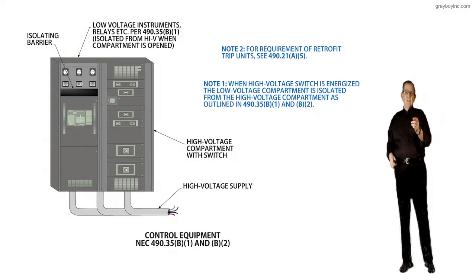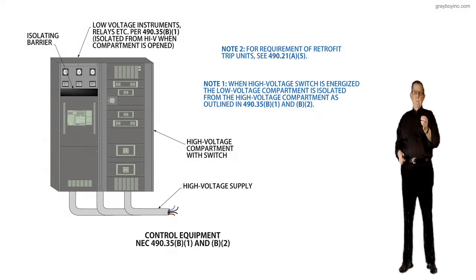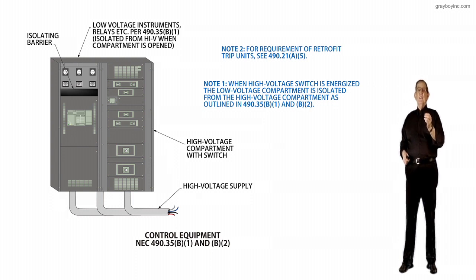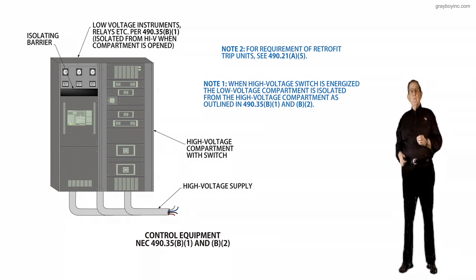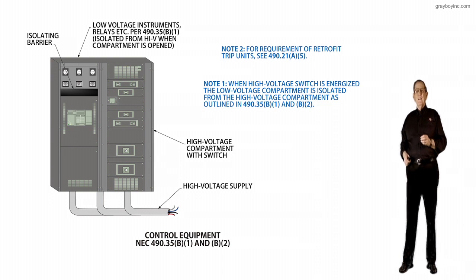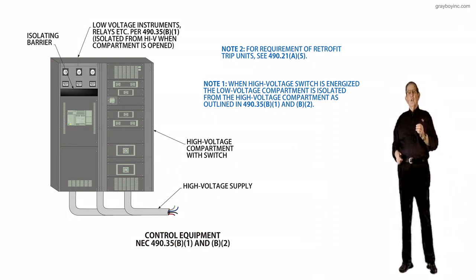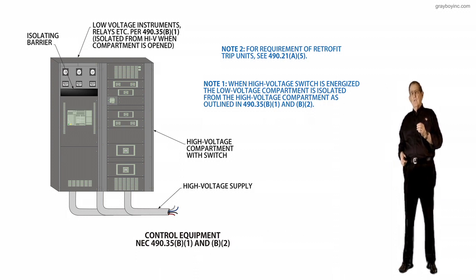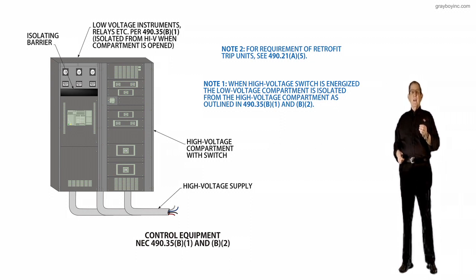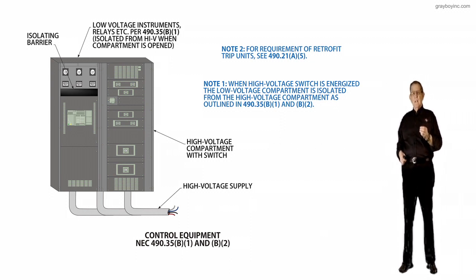This illustration deals with control equipment in accordance with 490.35 B as in boy 1 and B 2. The purpose of the change was to provide a revision, and this revision has been made to clarify the requirements for control equipment, relays, motors, and the like operating at 1,000 volts nominal or less.